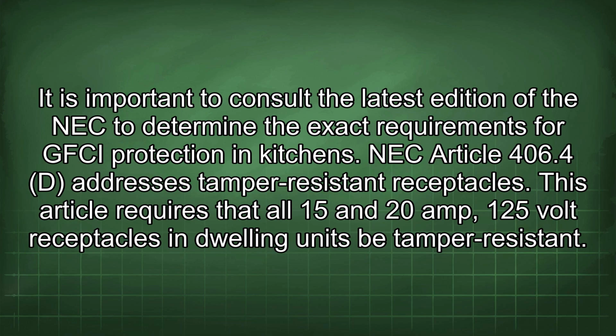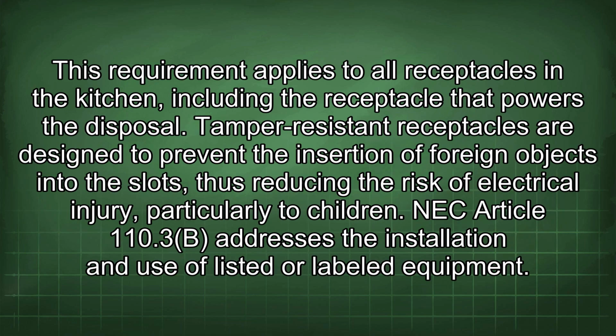It is important to consult the latest edition of the NEC to determine the exact requirements for GFCI protection in kitchens. NEC Article 406.4(D) addresses tamper-resistant receptacles. This article requires that all 15 and 20 amp 125 volt receptacles in dwelling units be tamper-resistant. This requirement applies to all receptacles in the kitchen, including the receptacle that powers the disposal. Tamper-resistant receptacles are designed to prevent the insertion of foreign objects into the slots, thus reducing the risk of electrical injury, particularly to children. NEC Article 110.3(B) addresses the installation and use of listed or labeled equipment.